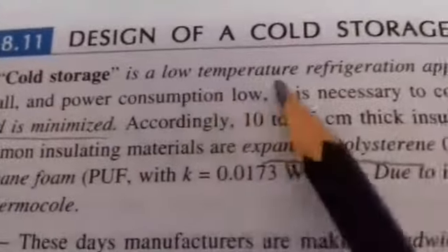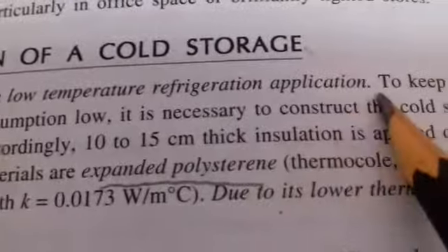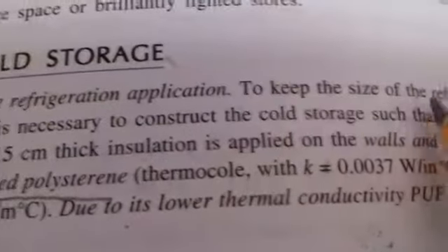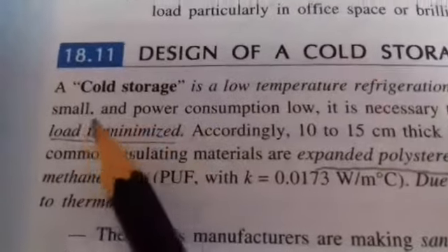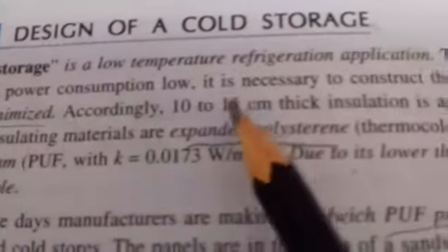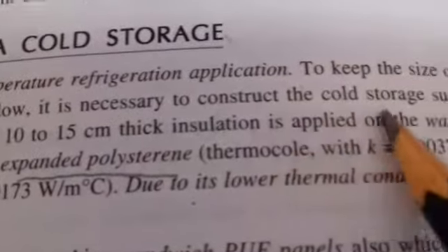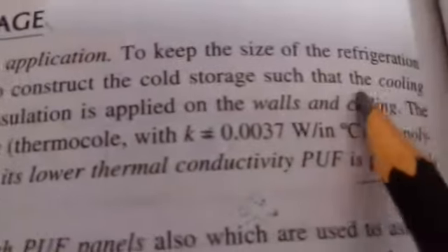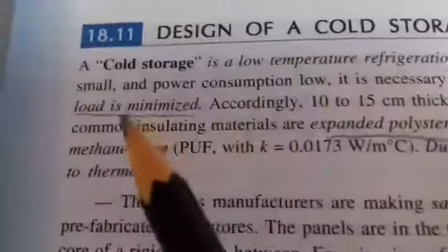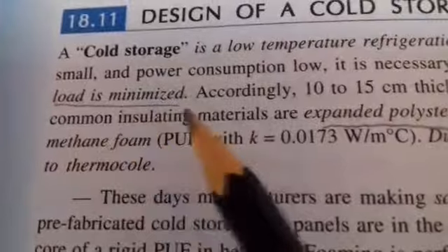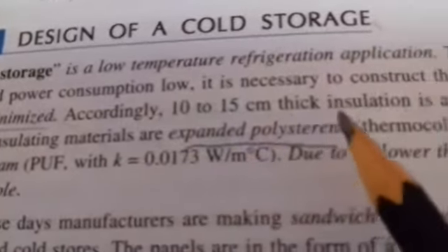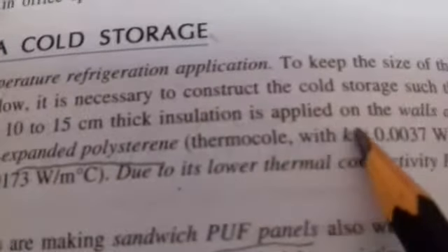Design of a cold storage. A cold storage is a low temperature refrigeration application, so the size of the refrigeration is small and power consumption low. It is necessary to construct the cold storage such that the cooling load is minimized. According to standards, 10 to 15 centimeter thick insulation is applied on the walls and ceiling.